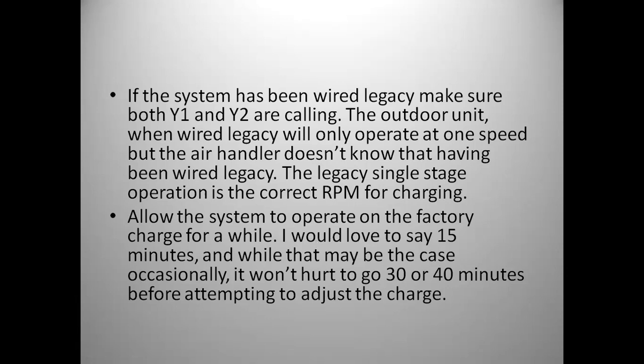my recommendation is, once you put it in charge mode or put it in high stage using the Y1, Y2, allow it to run for no less than 30, I would say 40 minutes minimum before you start adjusting your charge. At that point, it will be stable, and then you can make your proper adjustments.